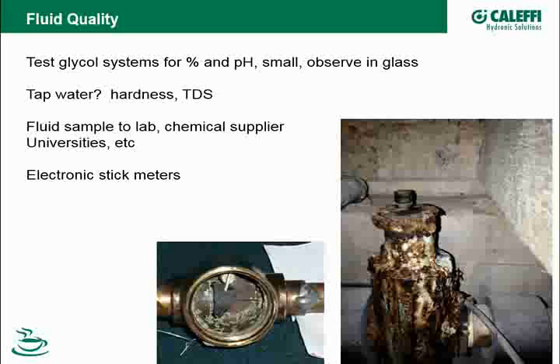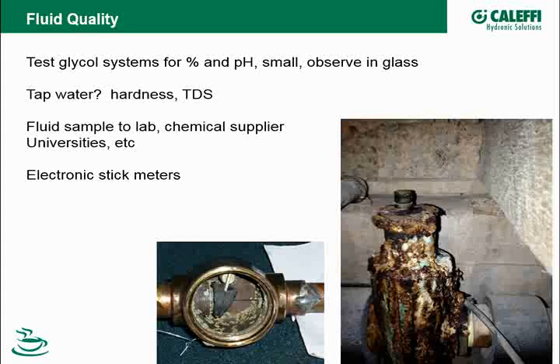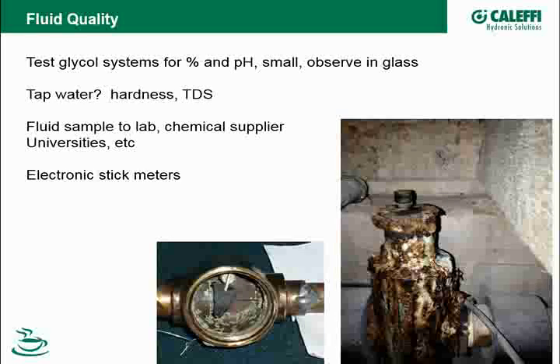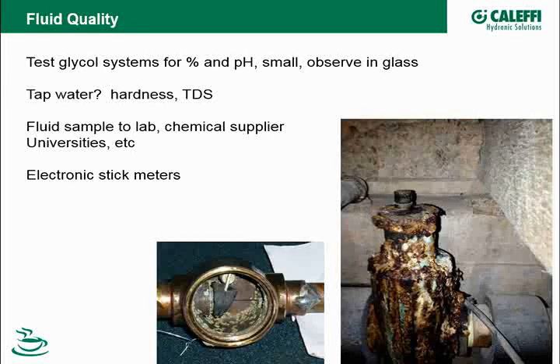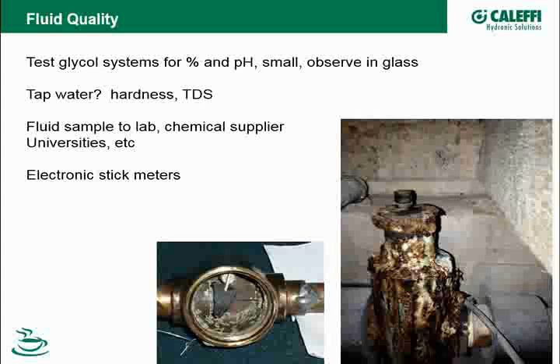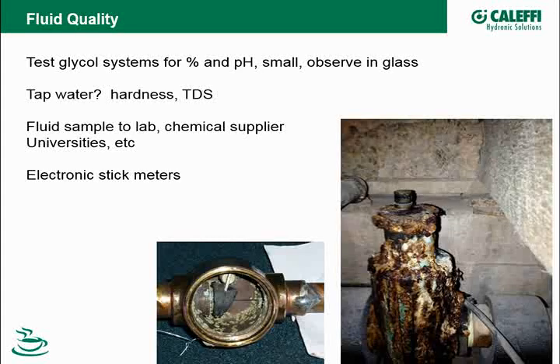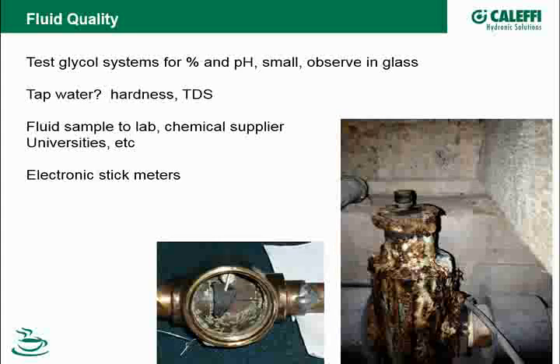And the other one that's critical is a little pH meter, because as glycol goes bad, the pH will start dropping. Typically when you put new glycol in a system, it'll have a pH of about 10.5 to 11.5. If for some reason there are conditions in the system where the inhibitors in that glycol are getting used up, it's going to show up as a decrease in pH. So as you go back there every year, every couple of years, you take a sample and you notice, well, gosh, now it's at 9 pH. I go back 2 years later, it's down around 8 pH.